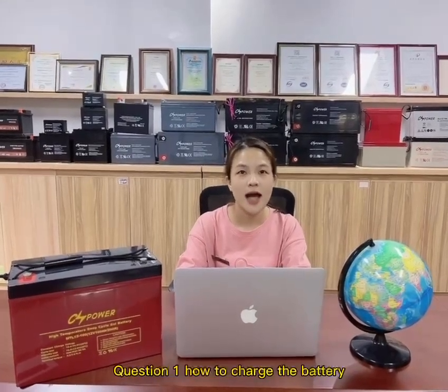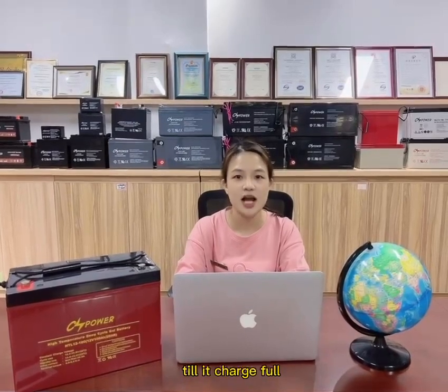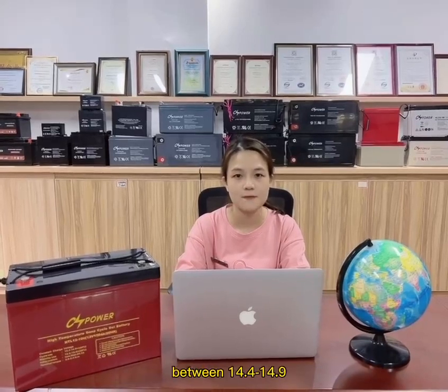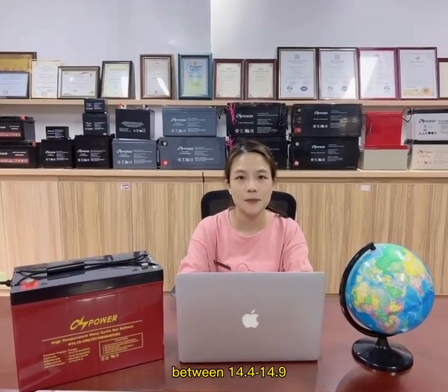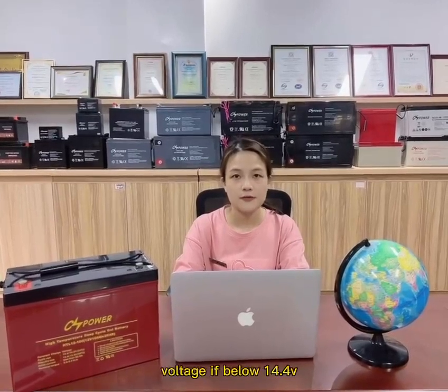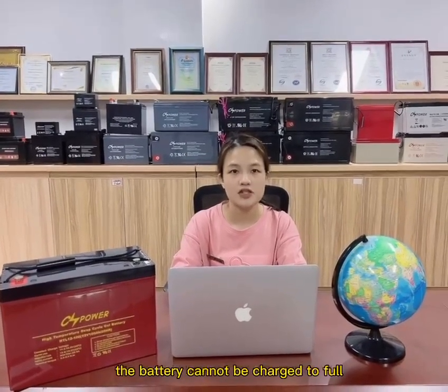Question 1: How to charge the battery till it charges full? Firstly, the charge voltage of the cycle solar yield must be set between 14.4 to 14.9 voltage. If lower than 14.4 voltage, the battery cannot be charged to full.